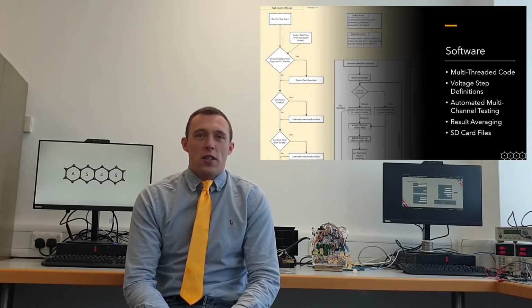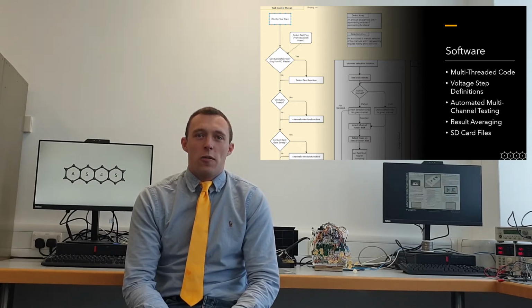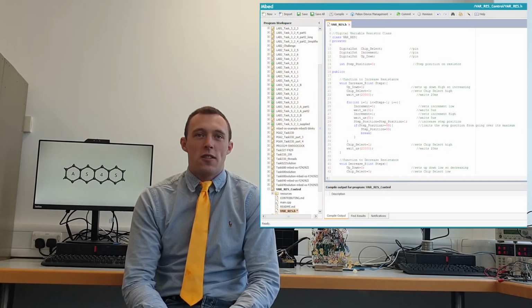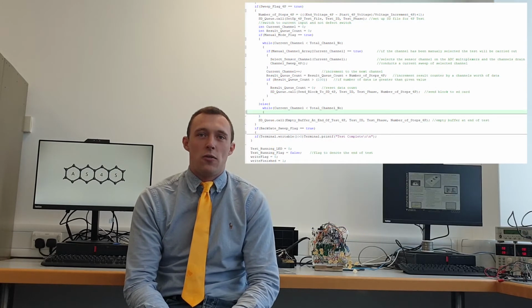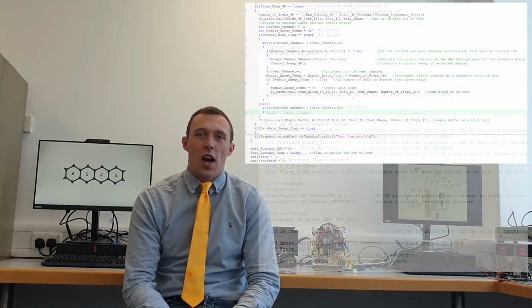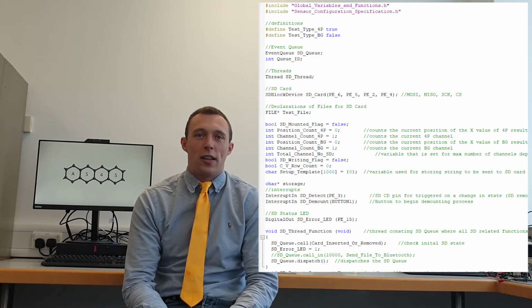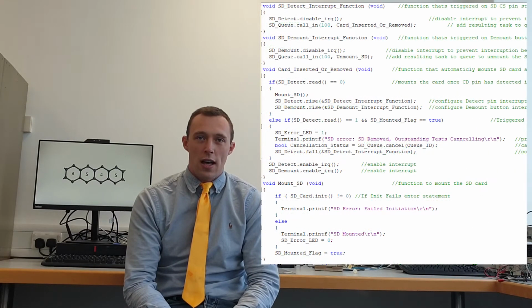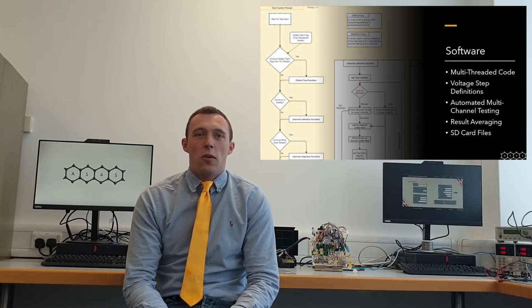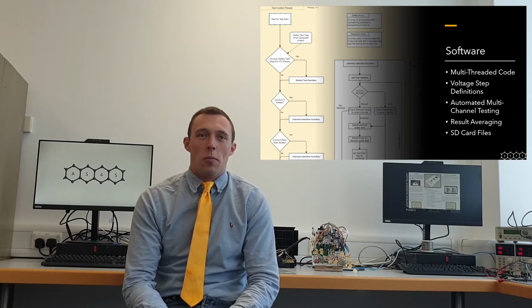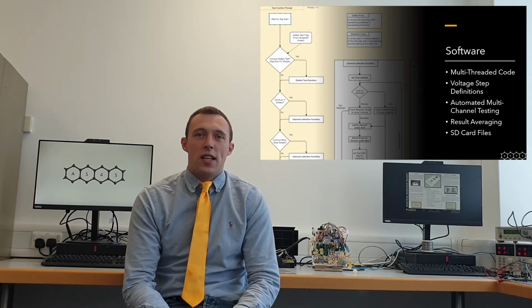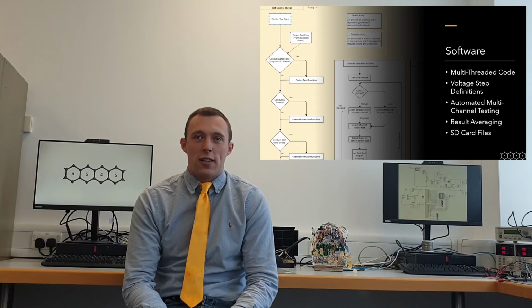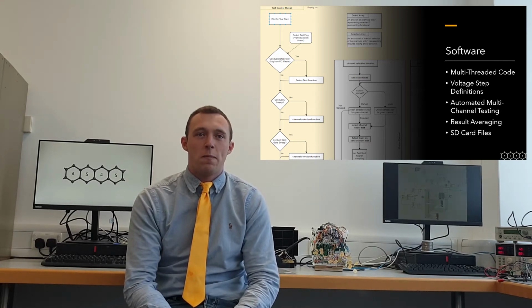To ensure a voltage is supplied for the test, an algorithm has been implemented that checks the voltage supplied from the variable resistors potential divider array, adjusting it up and down until each voltage value passed into the test is as close as it can be to the 1 mV required steps. The voltage is then passed through each of the sensors and different channels on the sensor selected one by one. This is repeated for each sensor and for each channel automatically and as per the definition supplied by the user when the test is configured.